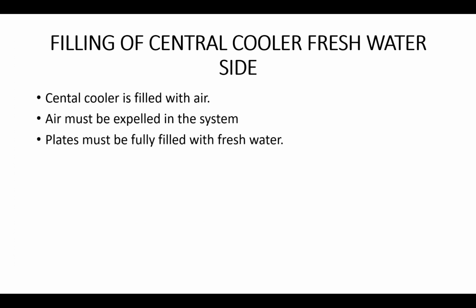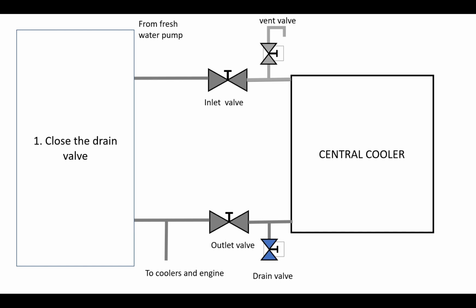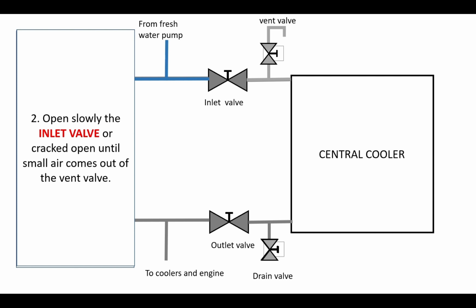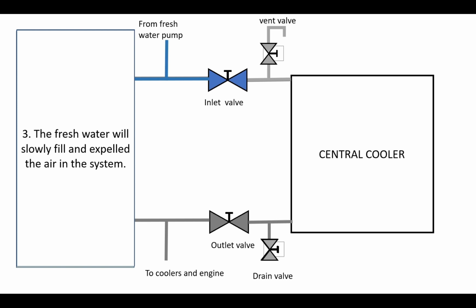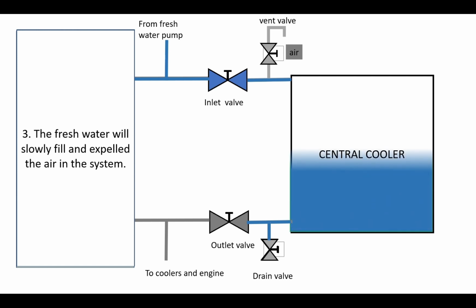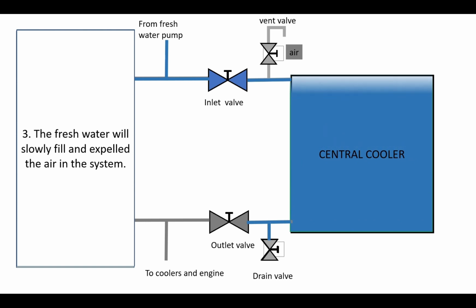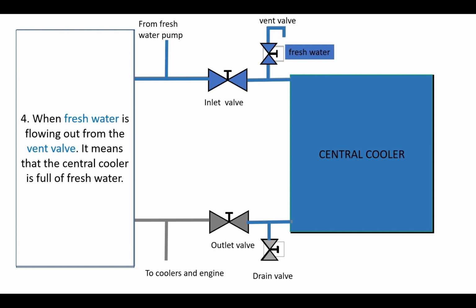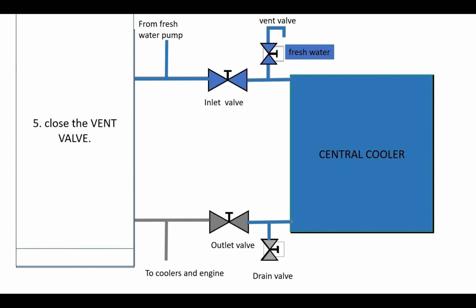The central cooler is filled with air, which must be expelled from the system. The plates must be fully filled with fresh water, and the flow will be from top going to bottom. First, close the fresh water drain valve. The low-temperature fresh water from the pump will be transported to the system. Open the inlet valve slowly, or crack it open, until air comes out from the vent valve. The central cooler will slowly fill with fresh water and the air will be expelled. When fresh water is flowing out from the vent valve, it means that the cooler is filled with fresh water. Close the vent valve.